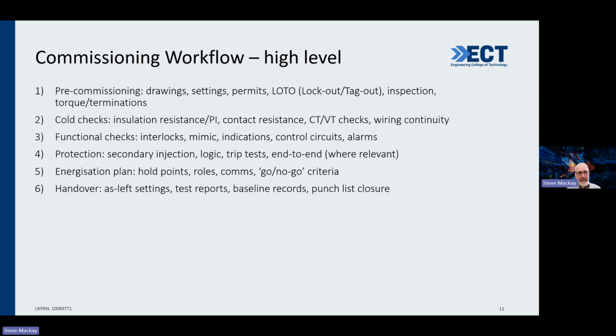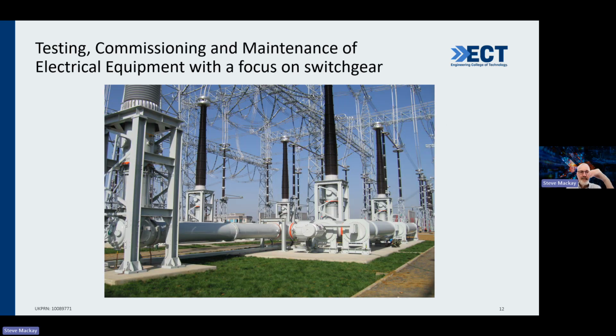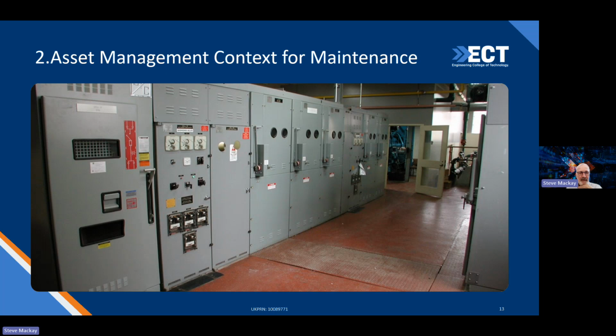So pre-commissioning drawings, lockout, tag-out, inspection, cold checks, insulation resistance, functional checks, things like interlocks, mimics, SCADA panels, protection, secondary injection, logic trip tests, energization plan, that's important, and then obviously the handover, and as left settings, test reports, baseline reports, punch list closures. Punch list at the end is always a massive pain, as you all know, walking around, opening the switch box and going through it and finding this termination hasn't been done, this hasn't been done properly, or it's missing a tag, going through all that and getting it remedied. Obviously, a lot of frustrating time spent on that. Anyway, so the topic today is obviously testing, commissioning, maintenance of electrical equipment. I just want to, as I say, go through some of the key issues there.